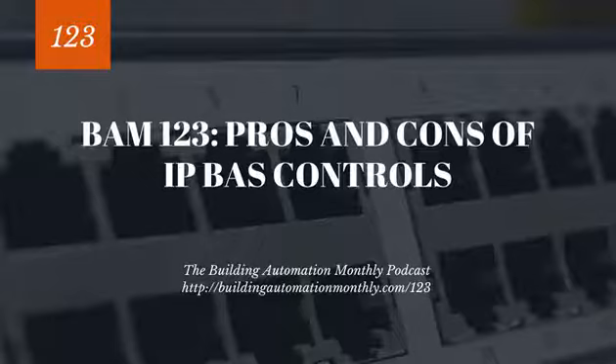Also, there's the issue of size. And this stretches actually across star, bus, and ring design patterns. Up to recently, we've always said, hey, give us a /24 subnet, give us 254 hosts, we'll put our supervisory devices on there. Maybe we'll even take a /26 network and get 62 hosts instead of a /24 where we get 254 hosts. Now here's the thing, I hear a lot of folks who are like, oh man, I could put all of my field controllers on this IP subnet. It would be awesome. And I'm like, remember, BACnet is primarily a broadcast protocol, at least in its local subnet. So as soon as you decide you want to put 1,000 devices on a subnet instead of 200, which I don't even recommend 200 on a single subnet, I recommend right around 64.